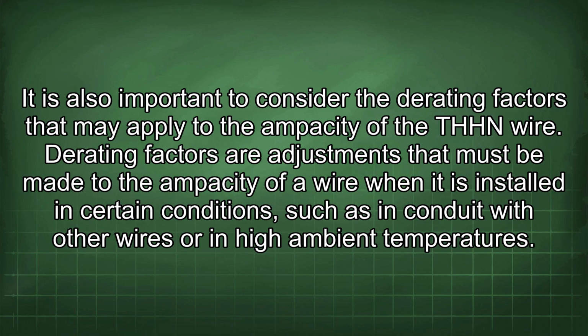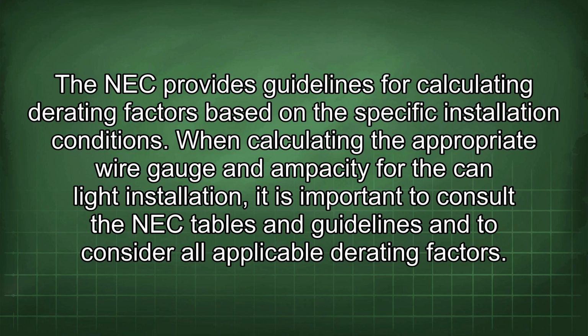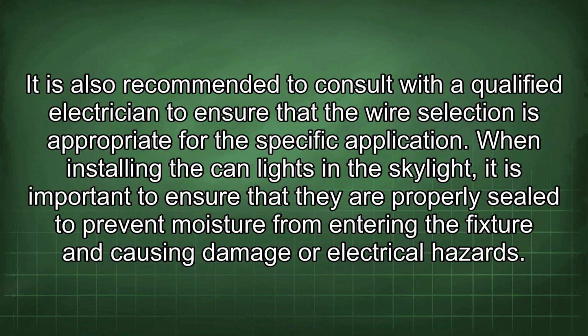Derating factors are adjustments that must be made to the ampacity of a wire when it is installed in certain conditions, such as in conduit with other wires or in high ambient temperatures. The NEC provides guidelines for calculating derating factors based on the specific installation conditions. When calculating the appropriate wire gauge and ampacity for the can light installation, it is important to consult the NEC tables and guidelines and to consider all applicable derating factors.